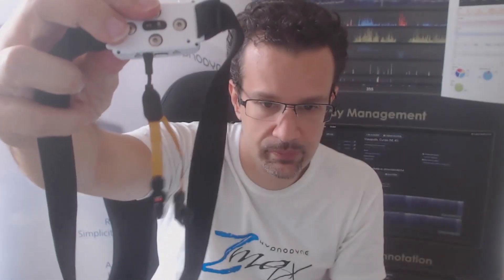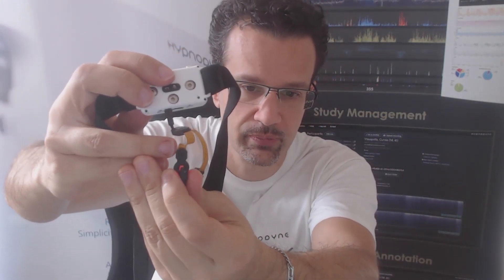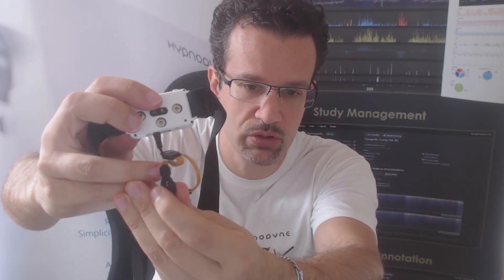So now to confirm that it's working, I simply switch this on. To actually check that it's working it needs to be transmitting in wireless mode, because otherwise it's not even sampling — it's just in standby, as you can see from the lights. There are two ways to take it out of standby: if you've got the HD recorder running it will do that for you, otherwise for simplicity you can just push the middle black key and it will set it to transmission mode. Now when this happens and the SpO2 sensor is plugged in, you will see a red light on the sensor itself. The fact that the red light is switching on and blinking very, very fast indicates that it's functioning correctly.